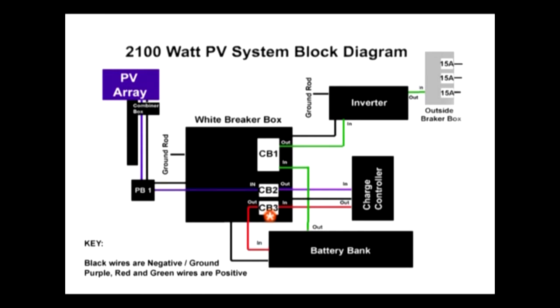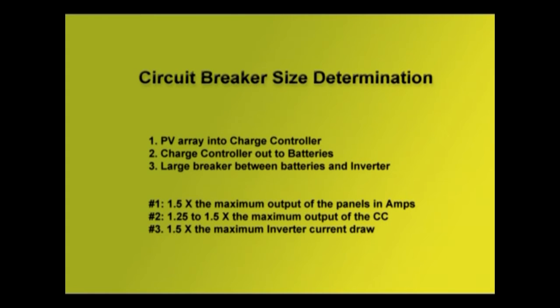The red comes back to circuit breaker 3 and then comes out of the breaker box again and goes to the battery bank plus. The green on the battery bank is also the plus of the battery bank, and it goes through the large circuit breaker on the top right, and that's our master shutoff for the inverter. That plus then comes out of the other side of the circuit breaker and goes out to the inverter's plus input. Then on this system, we do have a separate outside breaker box, and that has 3 15-amp breakers in it, and the AC outputs from the inverter go to it, and then the outputs from it go to the outlets in the house.